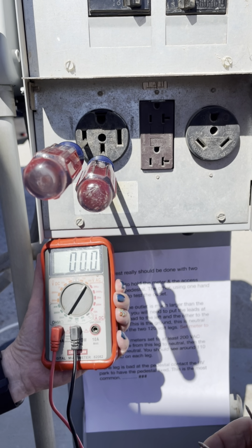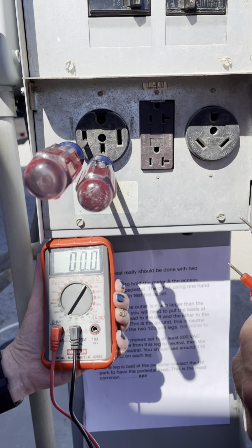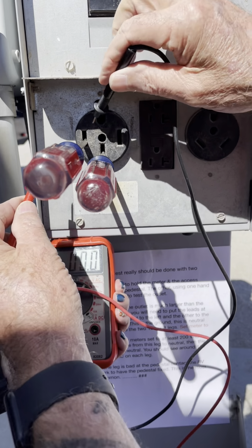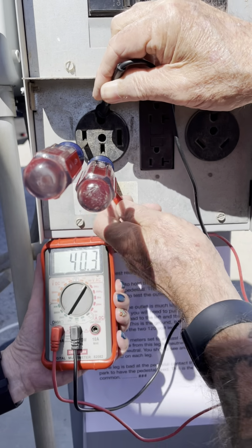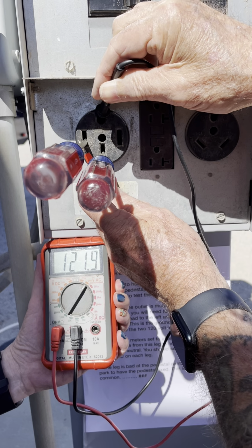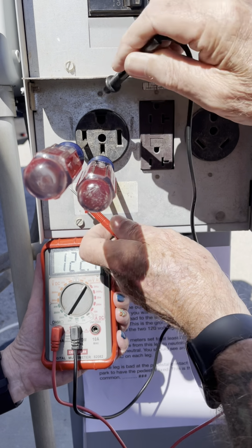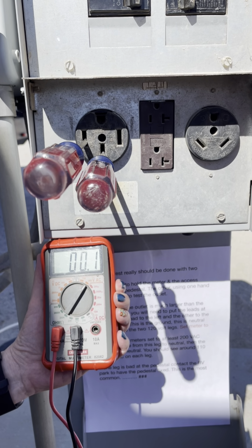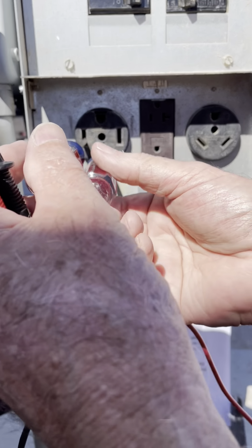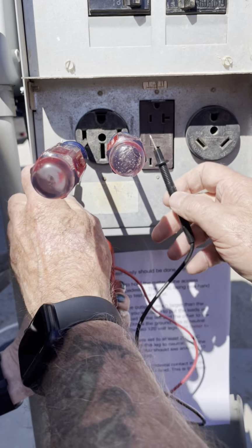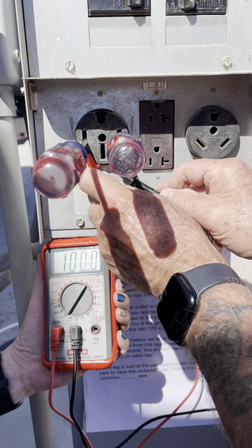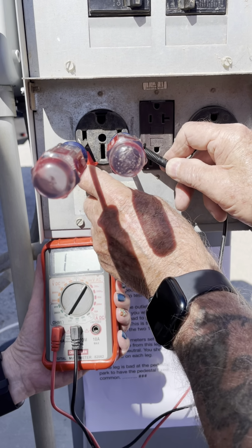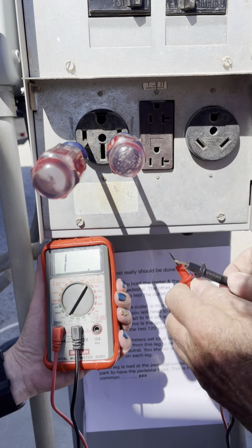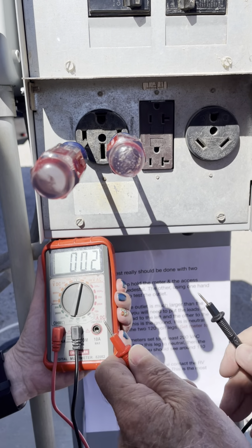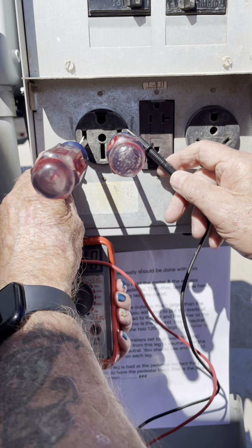Now, just to play it safe and make sure we don't have an open ground, I'm going to measure from ground to one of our legs, and we have another 120 volts. We also want to do the same thing from leg to leg, just as a double check. This should be something around 240 volts, but be sure to change the scale on your meter.